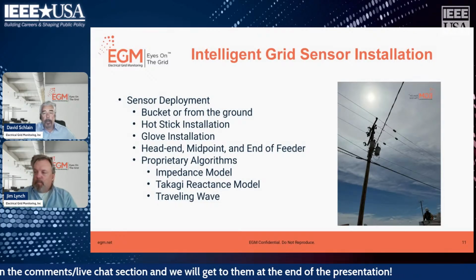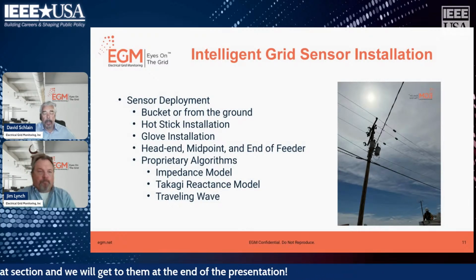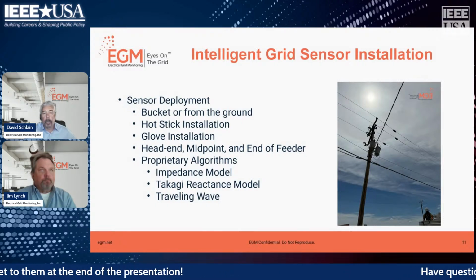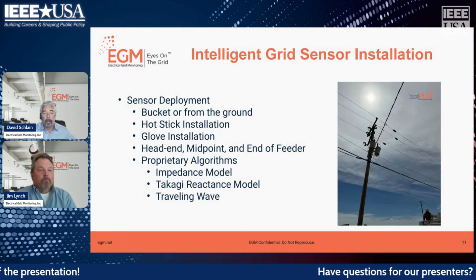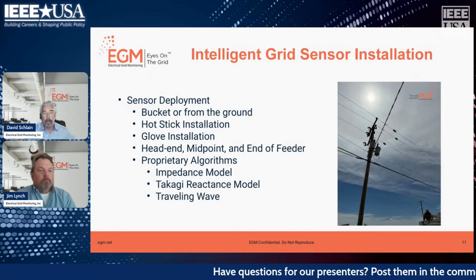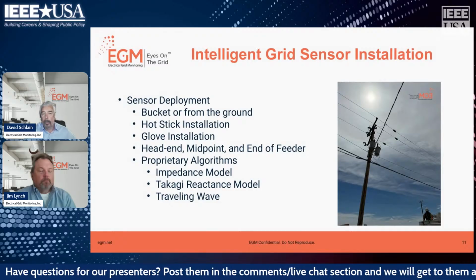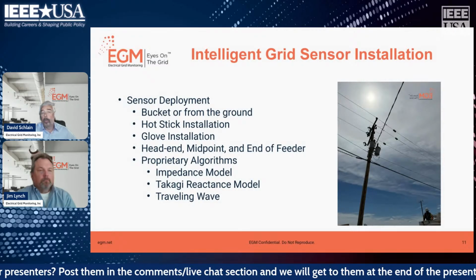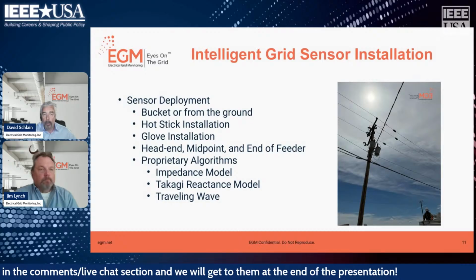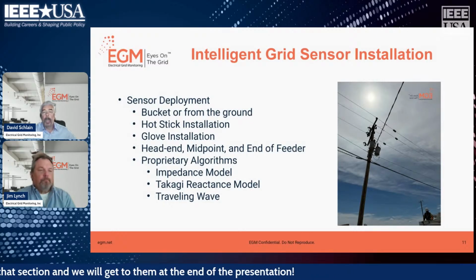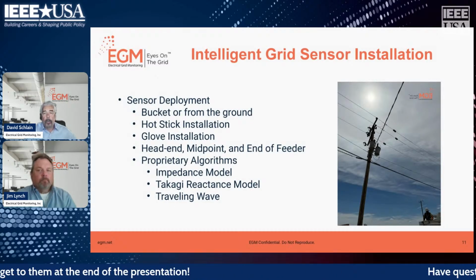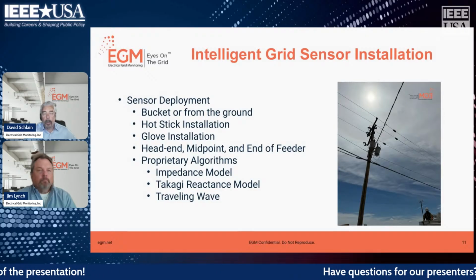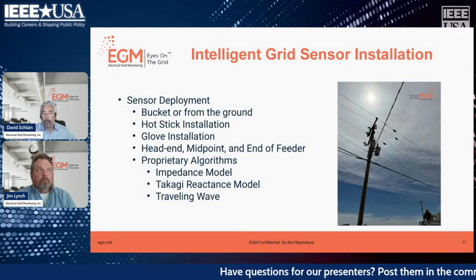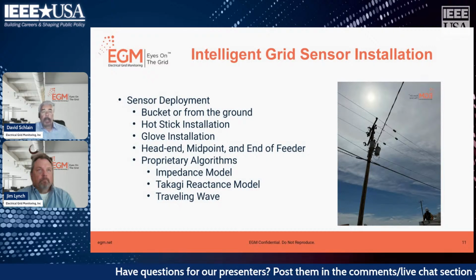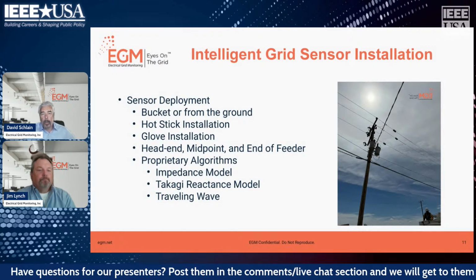As part of my experience at a chemical company, one of my responsibilities was operating and maintaining the station we had, which dropped from 138 kV to lower voltages for running our very high voltage motors and extruders. We used to have issues where our motors would only perform for half of their expected life, so we did some studies when I was there as an engineer.